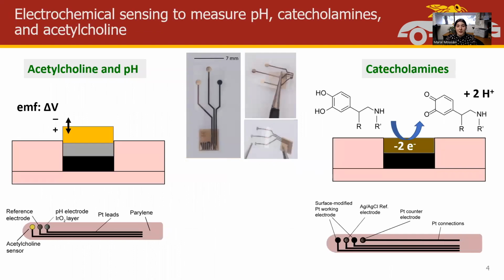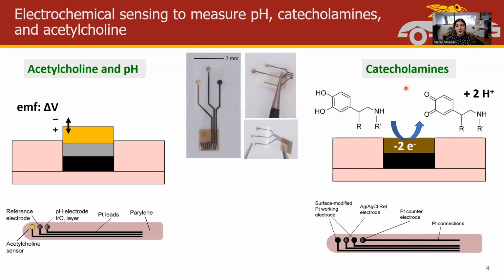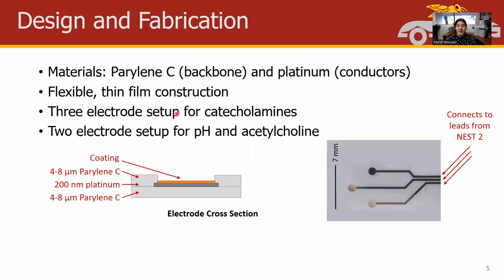What we're developing is two separate modules that could also be combined together, where you are able to pick either the catecholamine module or the acetylcholine and pH sensing modules. These are electrochemical sensors that can be implanted in vivo continuously for monitoring the levels and to provide feedback for closed-loop neuromodulation. We use two different mechanisms of sensing. We utilize electrochemical sensing, specifically oxidation of catecholamines, to enable antibody-free recognition and selective detection of these molecules. For acetylcholine and pH, we use a different sensing mechanism.